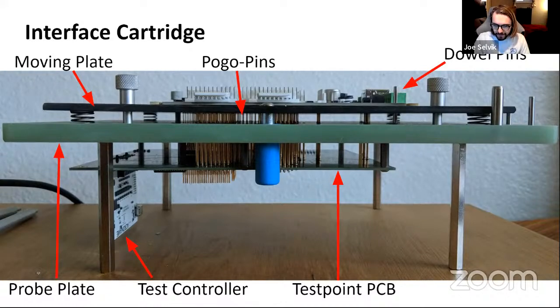If you move back up the image, you'll see that thinner black moving plate, which is what I was trying to describe. This is where the device under test sits flush. As it's pushed down onto those roughly 50 probes in this example, it helps distribute the force coming down from the pressure pins above.